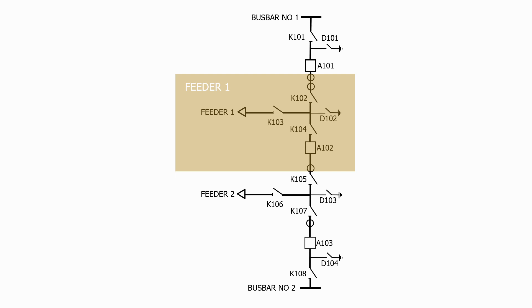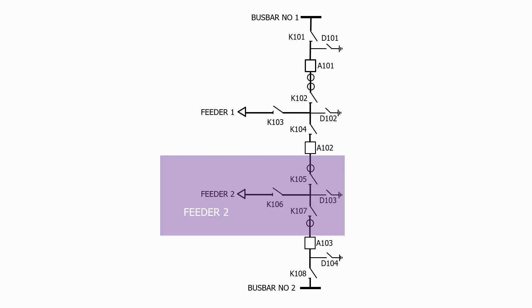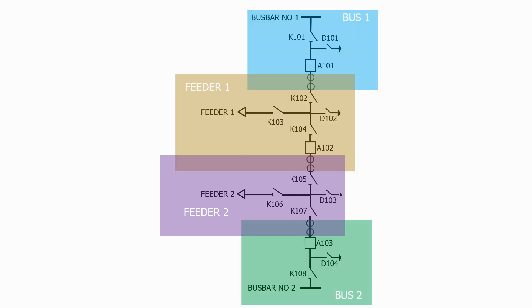What about the zone for feeder 2? Well, this follows the same principles as feeder 1. We need to overlap this protection zone with the others, so let's put the top current transformer in this position and the bottom current transformer here. Every piece of busbar and equipment on the circuit is now covered by one of the protection zones.